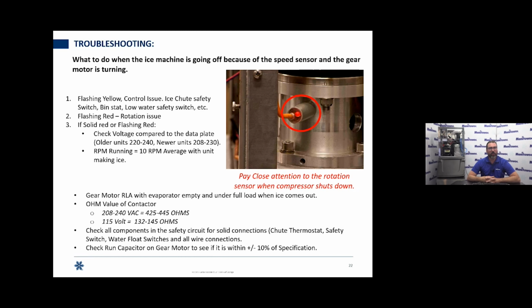We're going to have to verify all these conditions, verify that we have a proper ohm reading across that motor contactor coil. If we see conditions that look like there's nothing wrong, we can safely assume at that point that there's probably something wrong with the rotation sensor and that we're going to have to replace that. But again, make sure we have all our wiring connected properly, make sure we don't have any shorts to ground, anything like that that could be causing erratic readings or erratic current draws. Check the simple stuff first before automatically assuming we have a problem with the complicated thing.